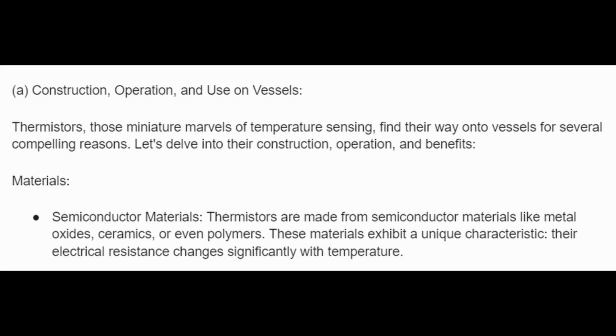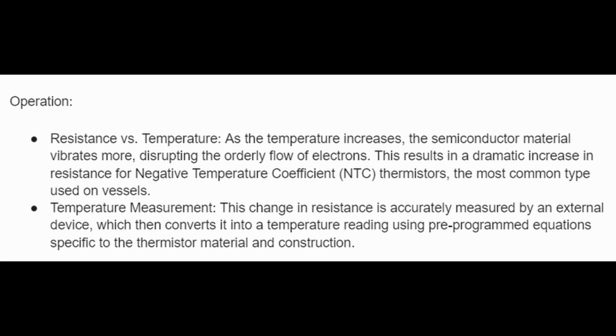Thermistors are made from semiconductor materials like metal oxides, ceramics, or even polymers. These materials exhibit a unique characteristic: their electrical resistance changes significantly with temperature. Operation. Resistance versus temperature. As the temperature increases, the semiconductor material vibrates more, disrupting the orderly flow of electrons. This results in a dramatic change in resistance for negative temperature coefficient (NTC) thermistors, the most common type used on vessels. Temperature measurement. This change in resistance is accurately measured by an external device, which then converts it into a temperature reading using pre-programmed equations specific to the thermistor material and construction.